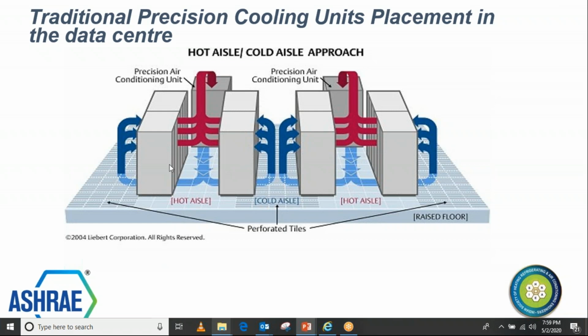There are different heights of racks. They could be 36U, 42U, 48, 52, 54. Typically these are 42U racks, and a rack sucks air from one side, typically the front, and the rear side of the rack will have hot air discharge after exchanging heat with the servers. So this hot air is supposed to go back to the cooling units, and the cooling units discharge cold air under the floor. You can see this is an access floor, a raised floor of a different height depending on the size of the data center and the kilowatts of the racks. Overall air is being pumped under the floor. Based on this, the size of the raised floor is decided.